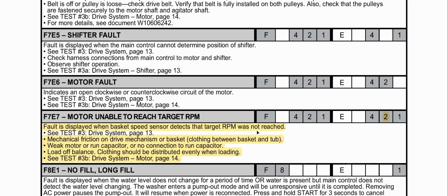But for some reason, the processor does not see the basket getting to 200 RPM. Maybe you have a bad sensor, or maybe there's a broken cable, so the actual speed of the basket never gets reported to the processor. Normally it waits about 10 seconds for the basket to reach 200 RPM, but today that's not happening. So what does the processor do? Usually the motor gets there 10 seconds later, but today it's not getting there. I've gone past 10 seconds - there must be something wrong with this machine, I'm gonna have to call it out.